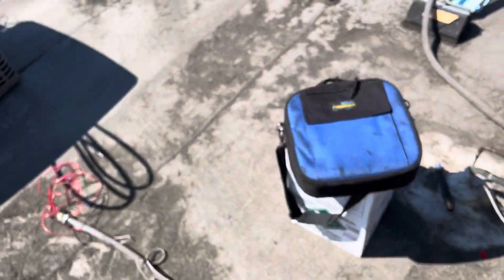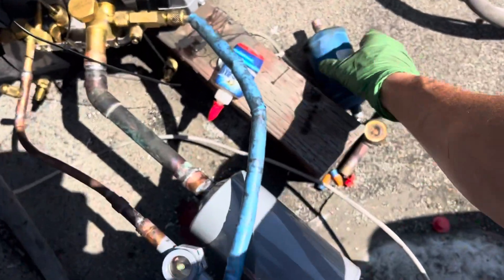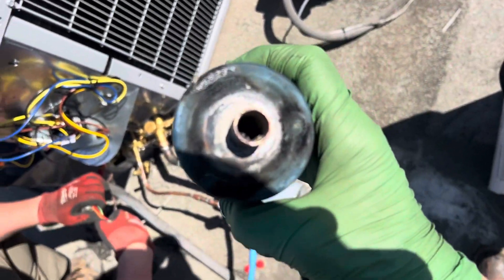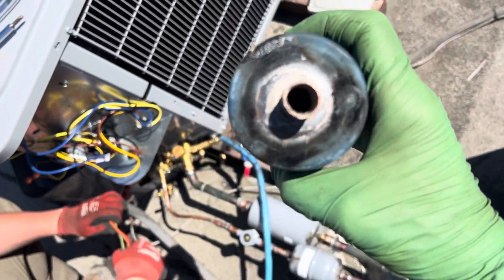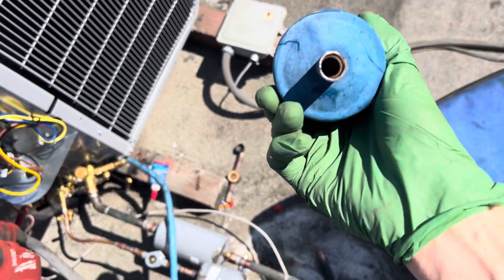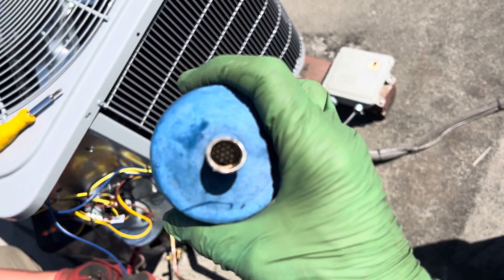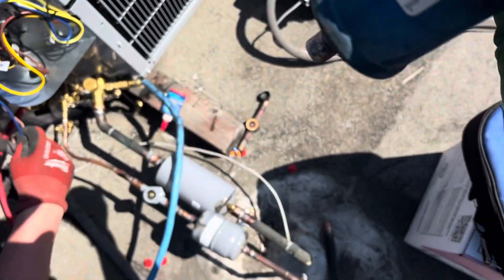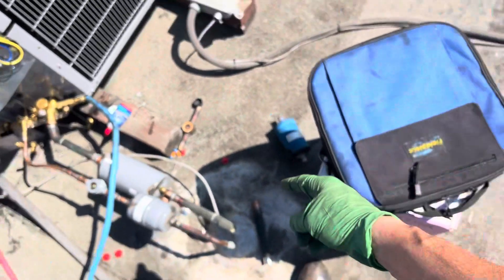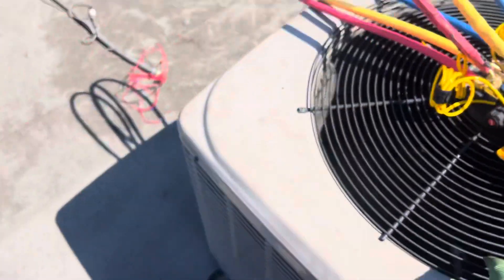In the last video I showed how black it is inside on the inlet, and then there's the liquid dryer. The outlet filter is still white — thank god. The guy who installed this apparently didn't see that it already had a filter inside one of the spun filters.